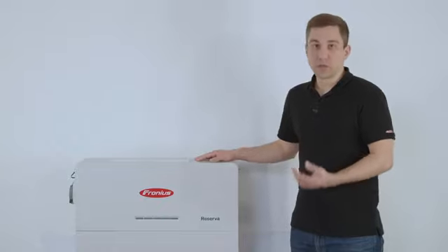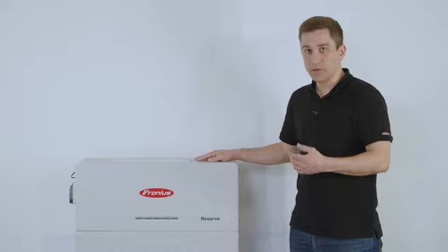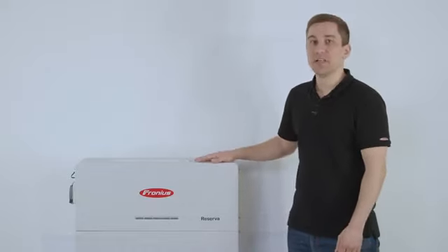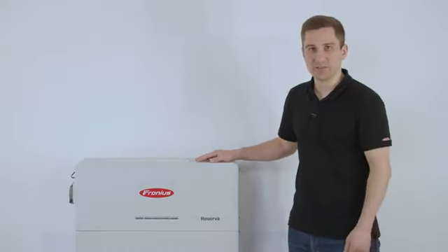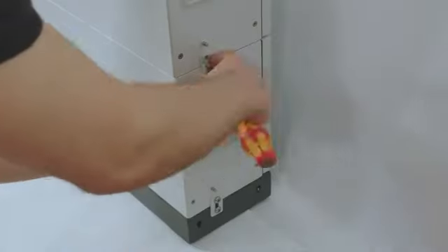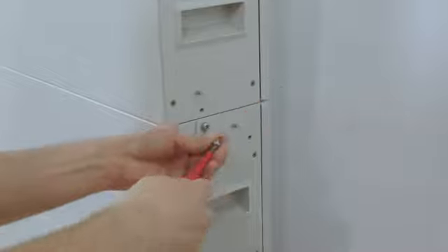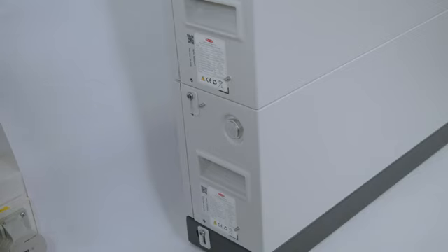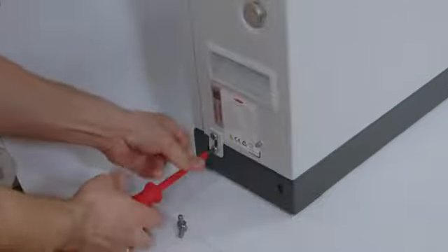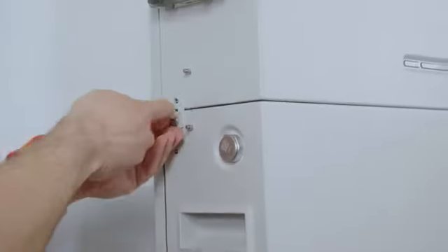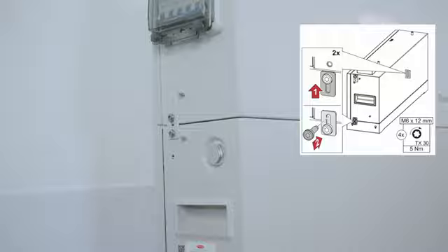Depending on how many modules you install per system, you have the choice between 2 up to 5 modules, and on the last module you place the battery management unit on top and screw it down the same way as you did with the modules. Please note that you need to do the mechanical screwing of the modules on both sides, so after screwing one side, please make sure to also fix the second side. To finalize the installation, please use a 5 Newton meter torque.